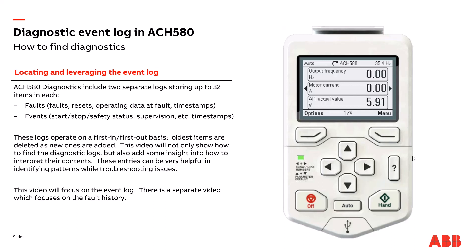An important item they have in common is that the entries in either log contain a timestamp. This provides great insight into the sequence of events not only within a particular log but also between the logs, as the timing of faults and events in the different logs can be cross-referenced to build a timeline of activity leading up to some incident that occurred with the drive.